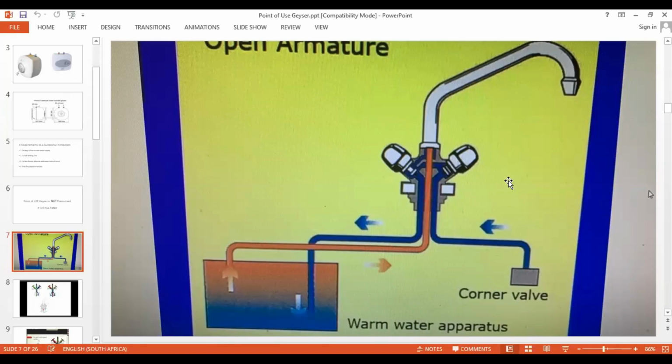The water in the vessel is going to heat up, it's going to push up through the spout and start dripping over and through. Please, the most important thing is once you have installed this, get the lady of the house and the domestic and explain to the people that when the geyser heats up, every time it goes through a heating cycle, the water is going to drip out of the nozzle. Very often, you will install this, you forget to tell the people, and they phone you and say, you've just installed this, you've left here half an hour ago, and it's faulty. We can't switch the water off. It keeps dripping and I keep turning the handle and it keeps dripping.